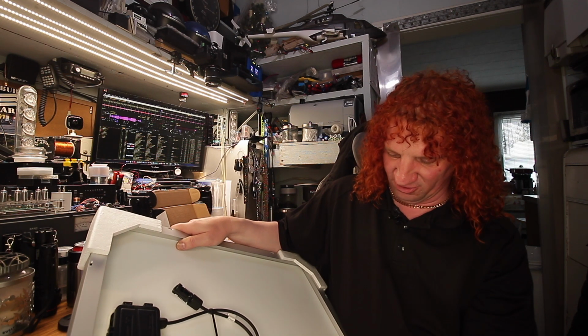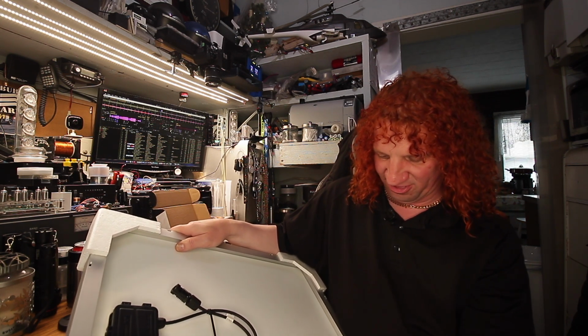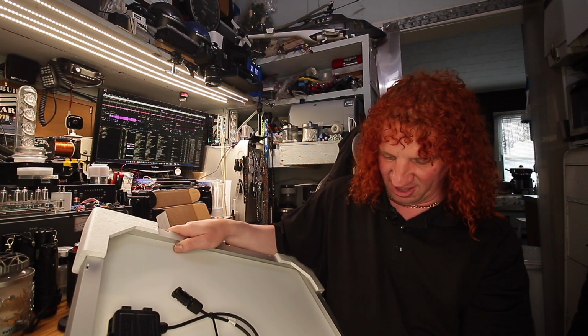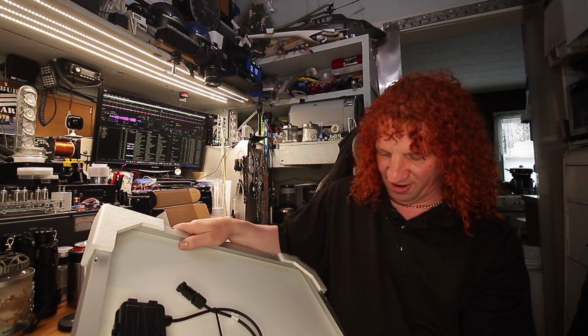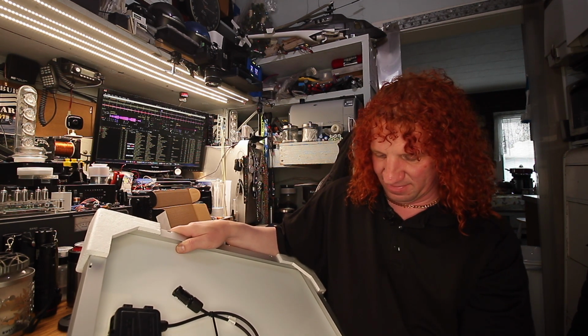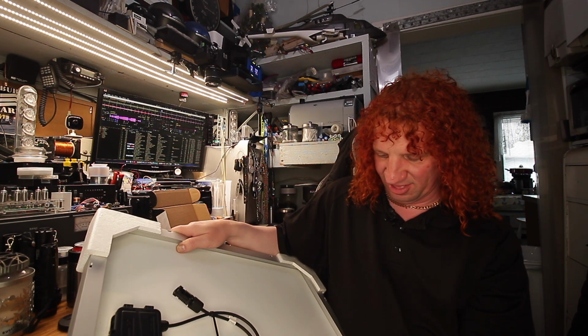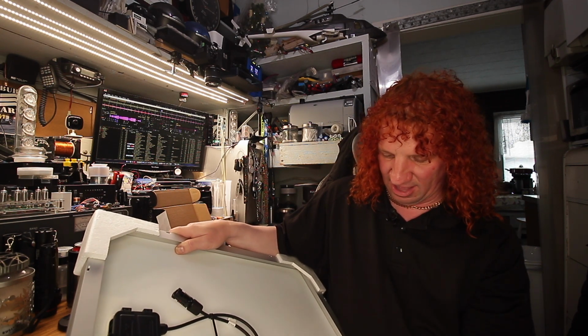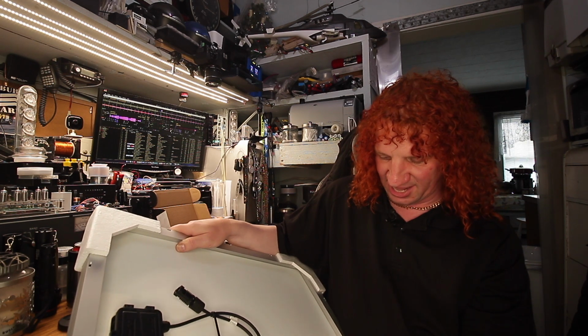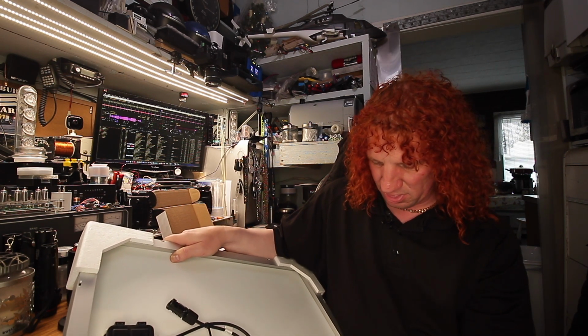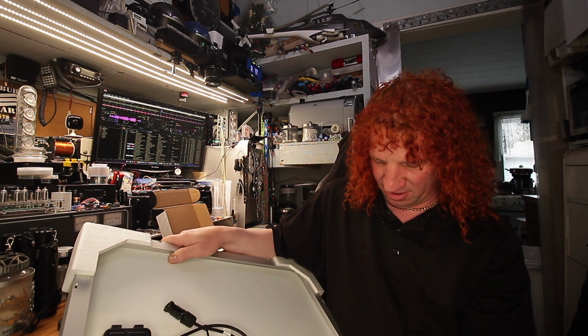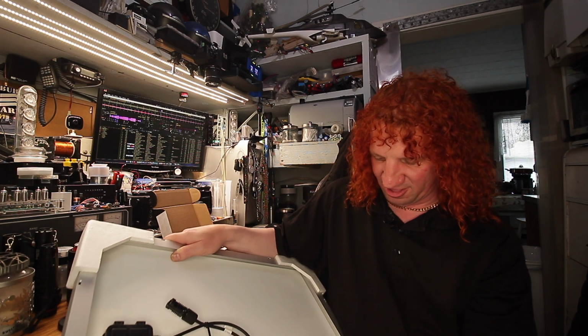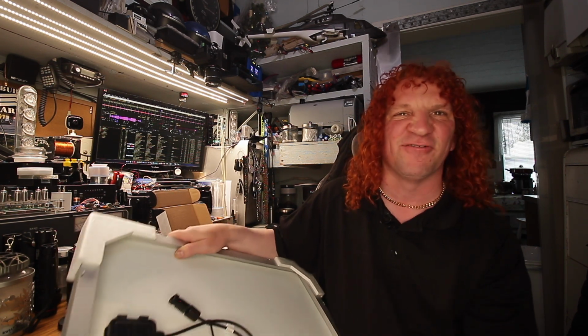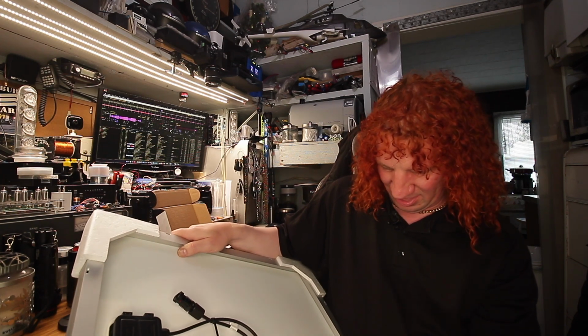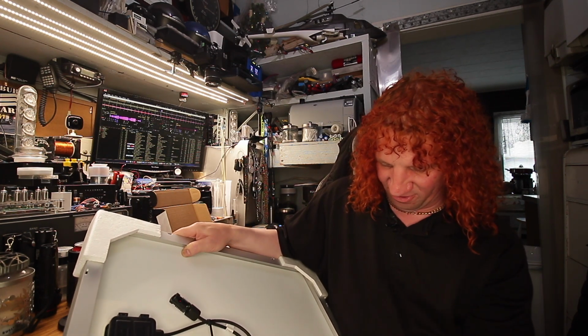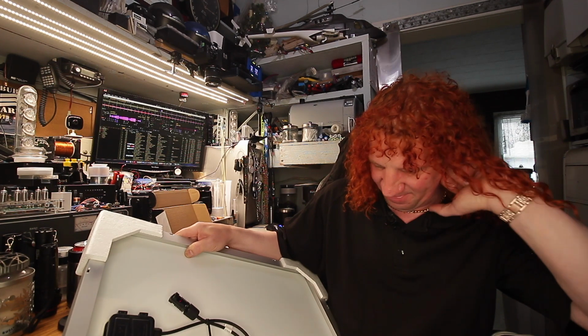Open circuit voltage is 22.3 volts, short circuit current is 2.94 amps, optimum operating voltage is 18.6, optimum operating current is 2.69 amps. The maximum system voltage this panel can handle is 600 volts, and the maximum series fuse is 15 amps.